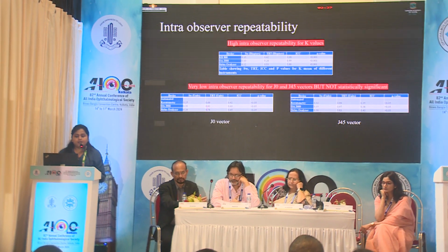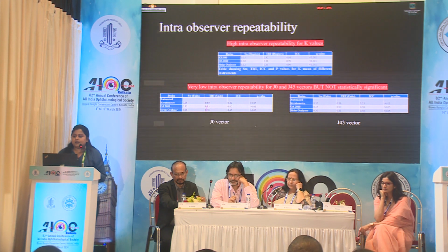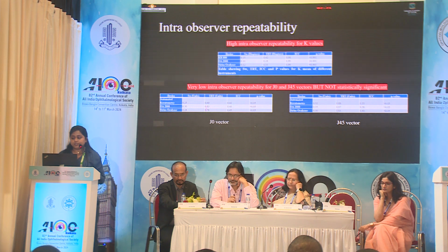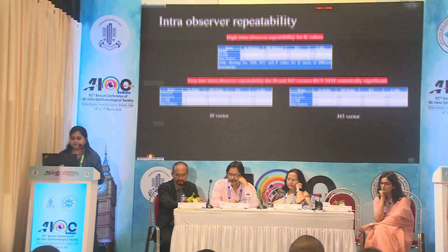Coming to the second part, intra-observer repeatability. Very high intra-observer repeatability was seen for K values, but not for J0 and J45 vectors. But this low repeatability was not significant. For all 3 devices, 1 or 3 readings are sufficient because of good repeatability.